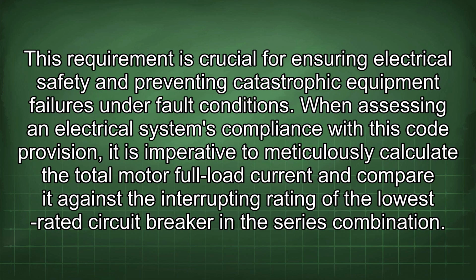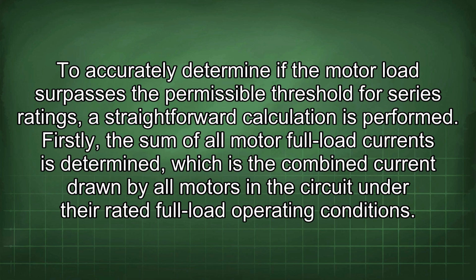This requirement is crucial for ensuring electrical safety and preventing catastrophic equipment failures under fault conditions. When assessing an electrical system's compliance with this code provision, it is imperative to meticulously calculate the total motor full load current and compare it against the interrupting rating of the lowest rated circuit breaker in the series combination. To accurately determine if the motor load surpasses the permissible threshold for series ratings, a straightforward calculation is performed.